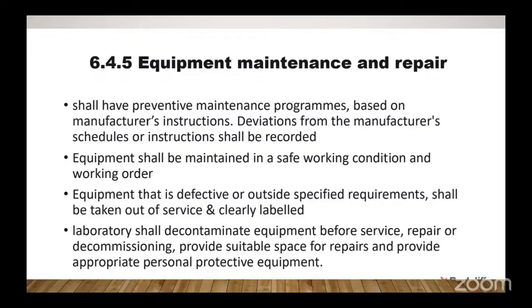Laboratory shall decontaminate equipment before servicing, repair, and decommissioning. So before the equipment is repaired, the engineer or yourself, you have to decontaminate it. Then when you want to decommission equipment, you have to decontaminate it. And there must be a proof, evidence of your decontamination.